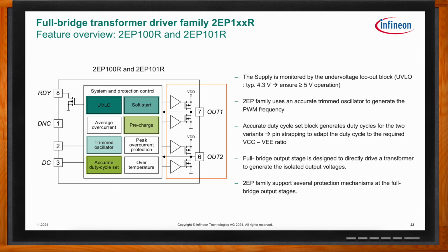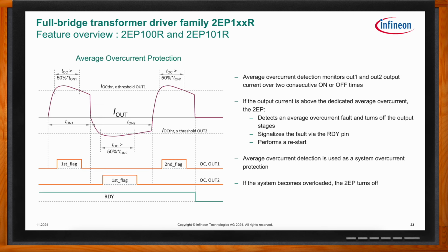Average overcurrent detection monitors out 1 and output 2 current over two consecutive on and off times. If the output current is above the dedicated average overcurrent threshold for more than 50% of the time, the 2EP detects an average overcurrent, turns off the output stage, sends a fault signal to the ready pin, and performs a restart.